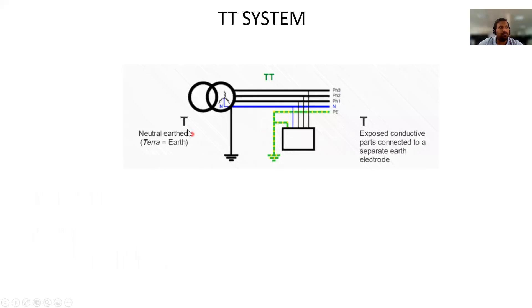The first type is the TT system. In the TT system, the supply-side neutral is earthed and the load-side equipment protective conductor is also earthed independently. Both the supply side and the load side have their own separate earth connections.